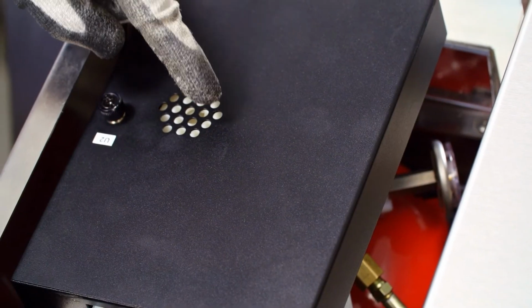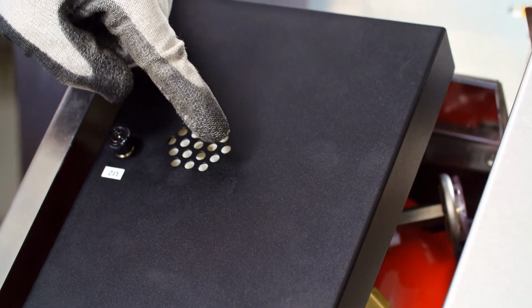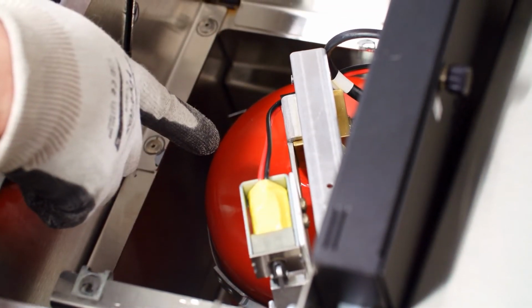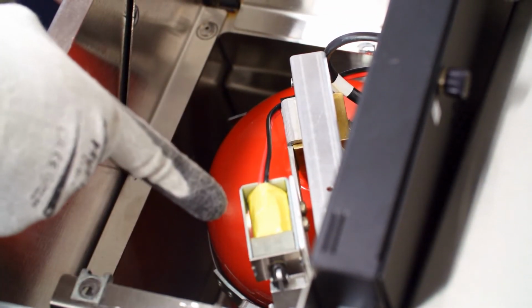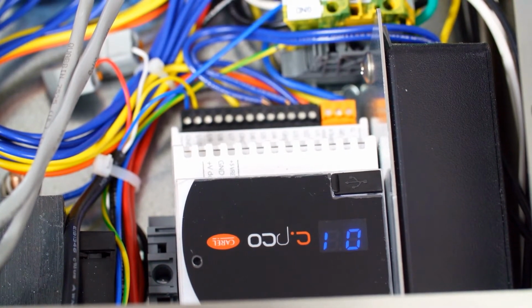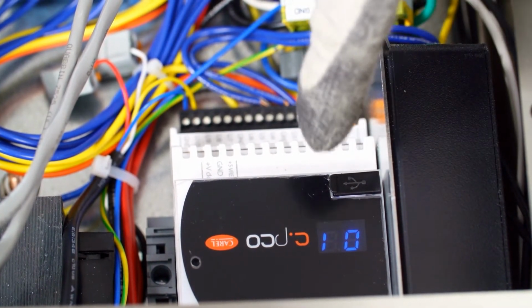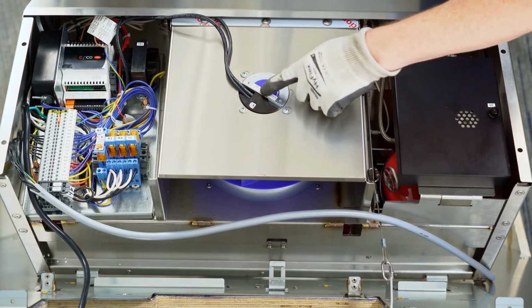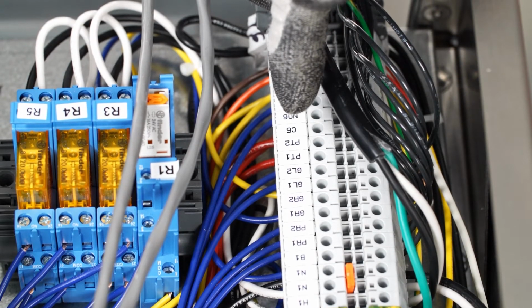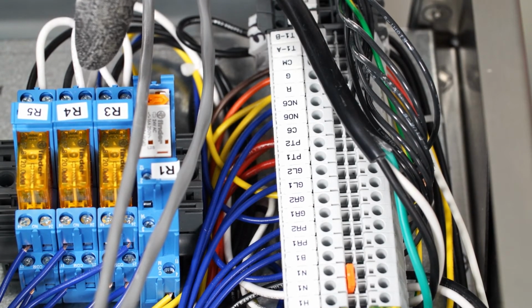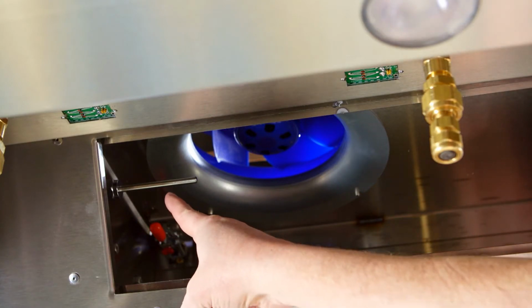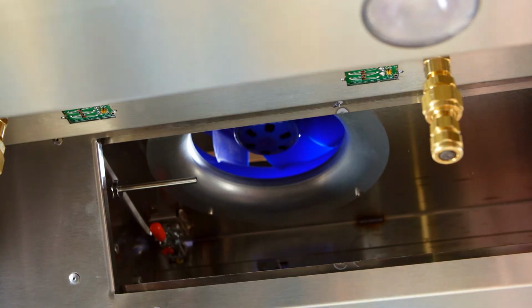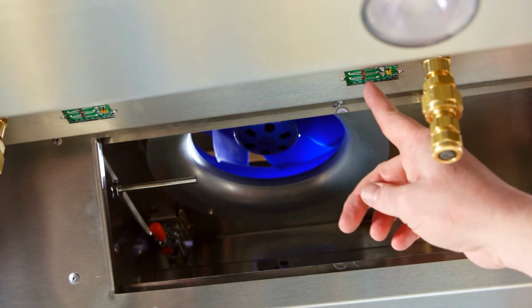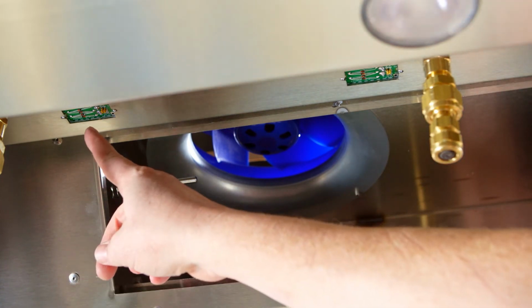This is the fire suppression control board. Here we can see the fire suppression tank and solenoid release. This is the programmable logic controller. In this particular hood, we have an internal exhaust fan, although your hood may have a fan external to the hood instead. This is a terminal block strip. These are relays. This is your 1 temperature sensor, and these are your fire system sensors 1 and 2.